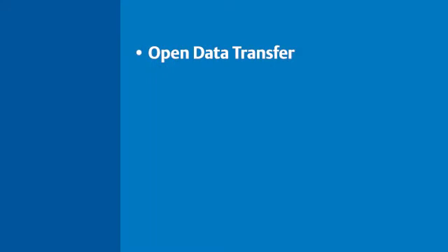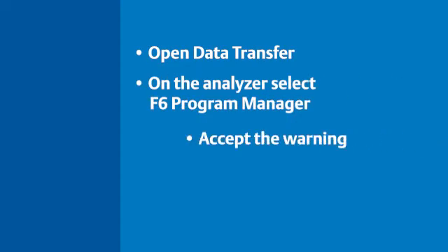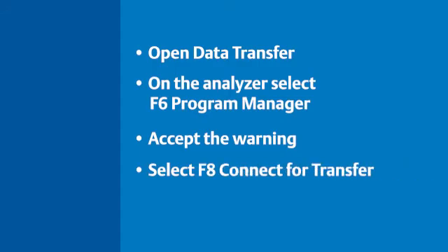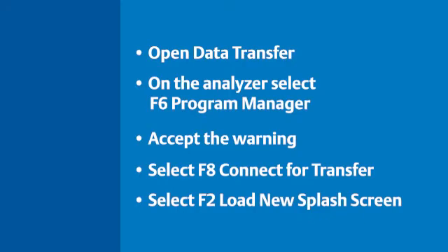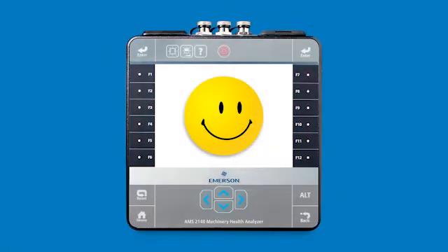With the Data Transfer tab of AMS Machinery Manager open, you can now start the AMS 2140 and select F6 Program Manager. Accept the warning and select F8 Connect for Transfer. Select F2 Load New Splash Screen. And now your customization is complete.